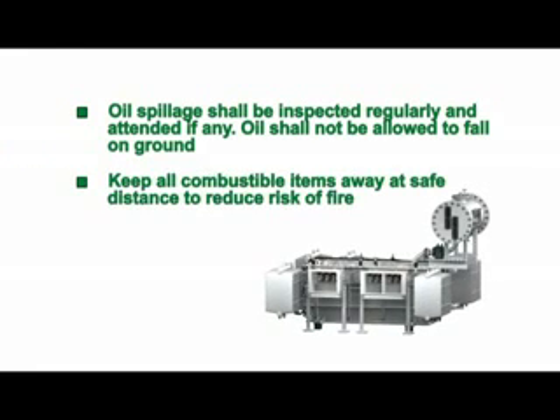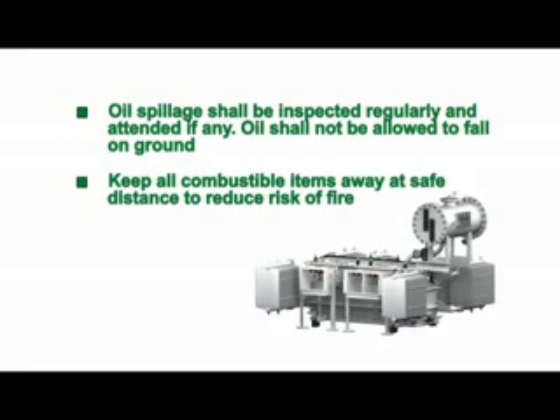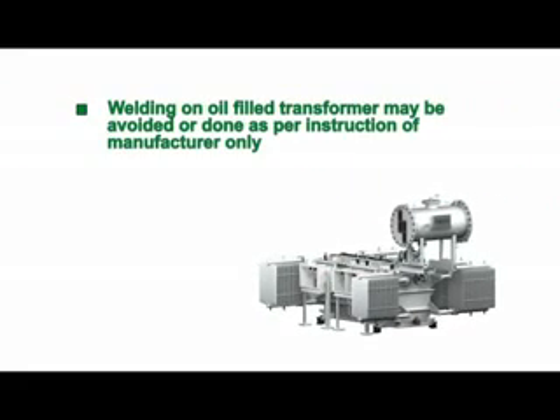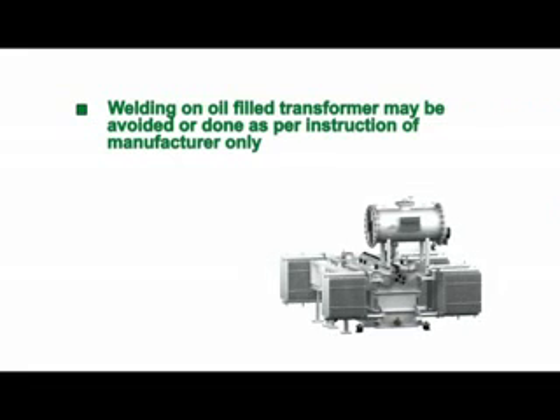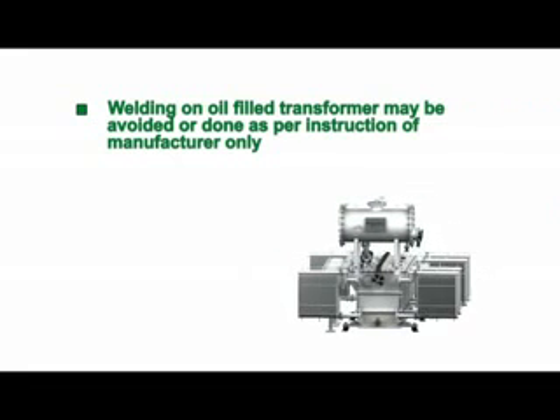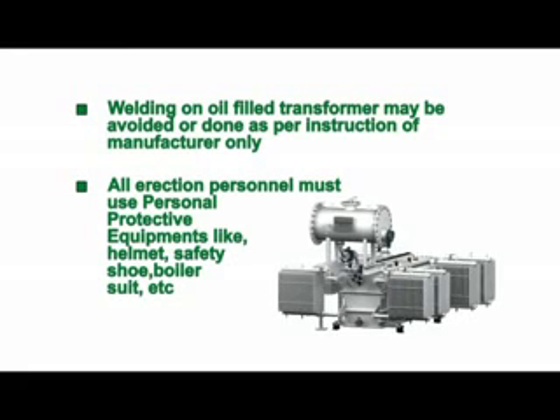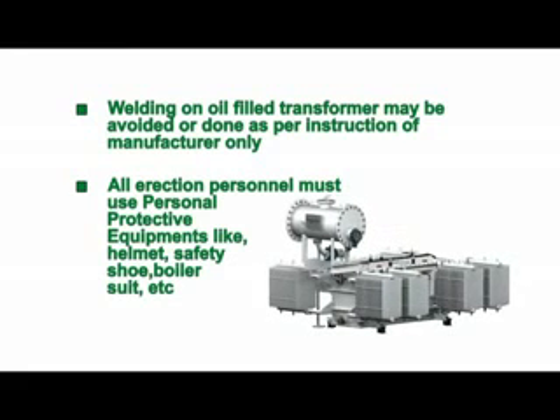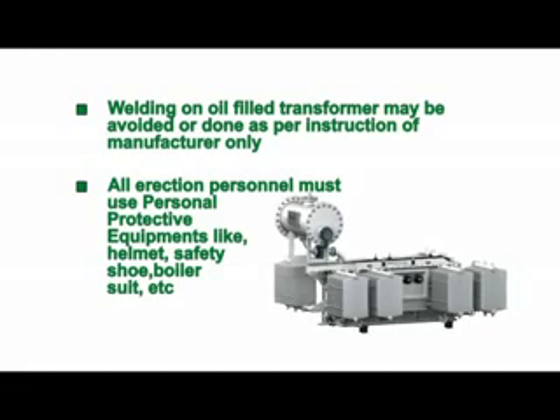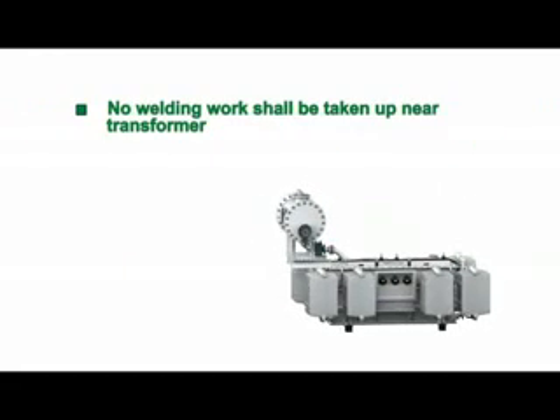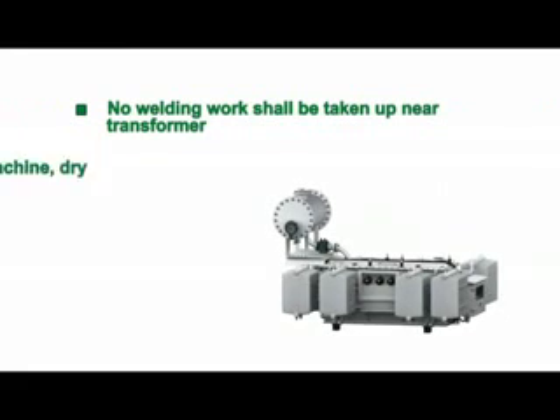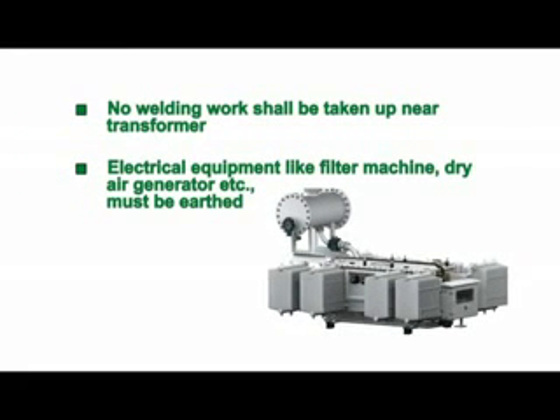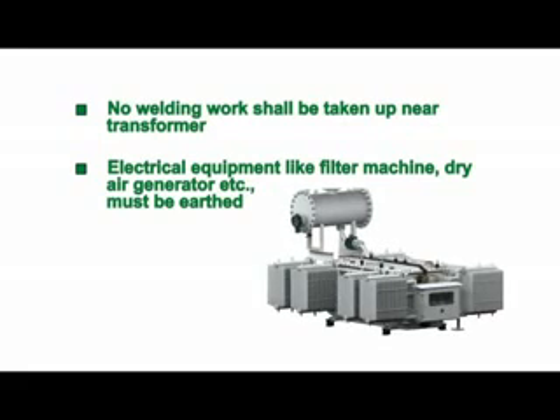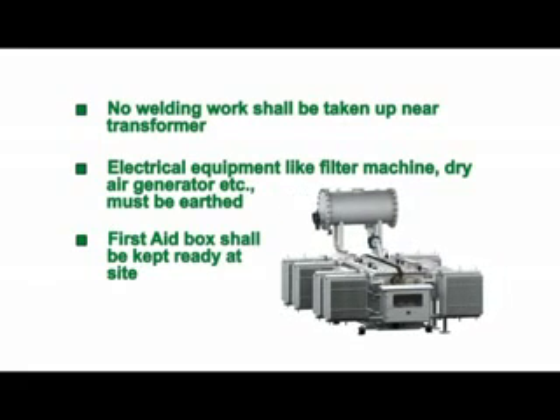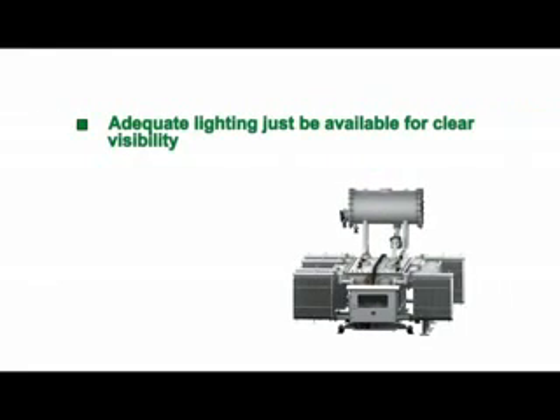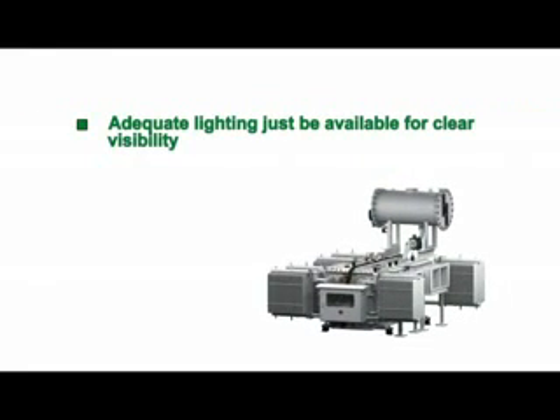Keep all combustible items at a safe distance to reduce the risk of fire. Welding on an oil-filled transformer may be avoided or done as per instruction of the manufacturer only. All erection personnel must use personal protective equipment like helmet, safety shoes, boiler suit, etc. No welding work shall be taken up near the transformer. Electrical equipment like filter machine, dry air generator, etc. must be earthed. A first aid box shall be kept ready at site. Adequate lighting must be available for clear visibility.